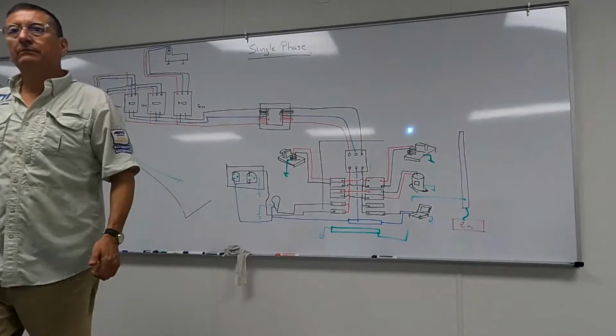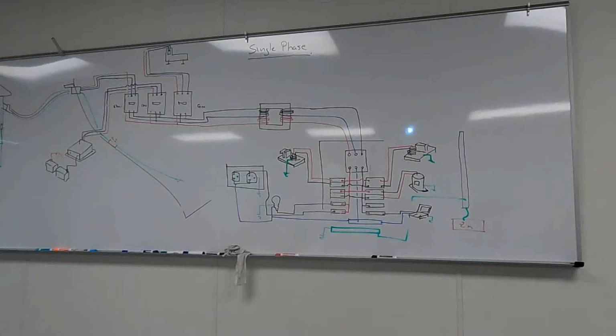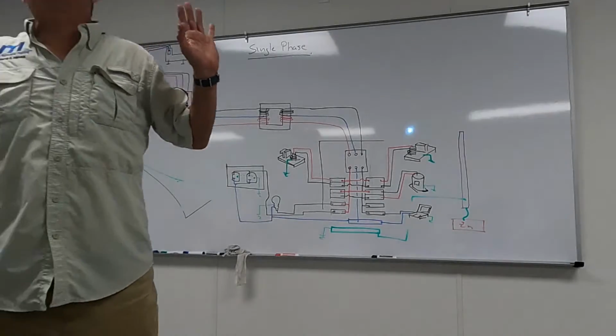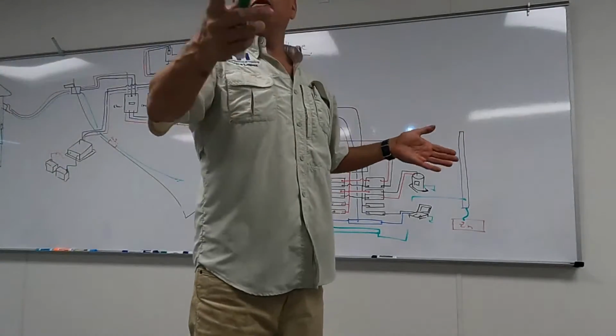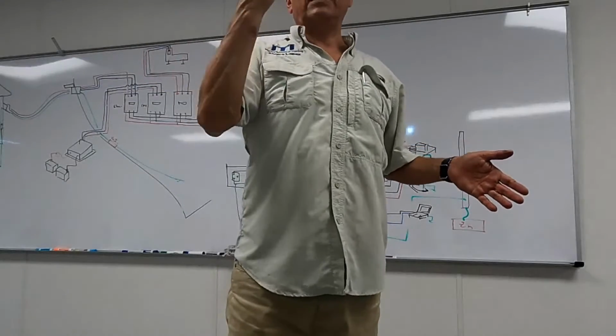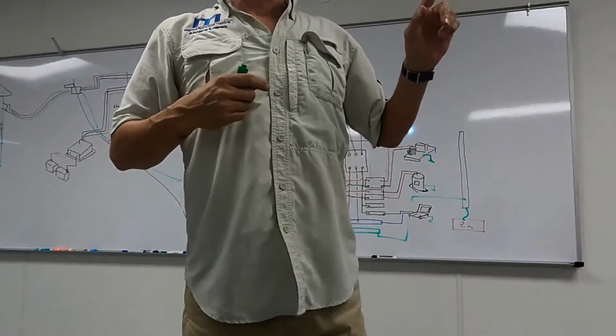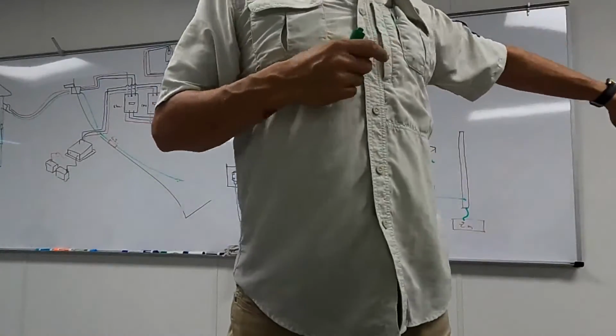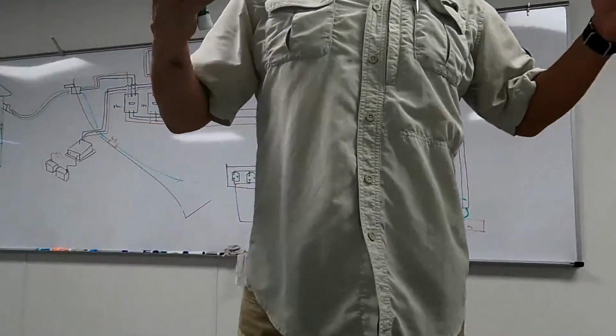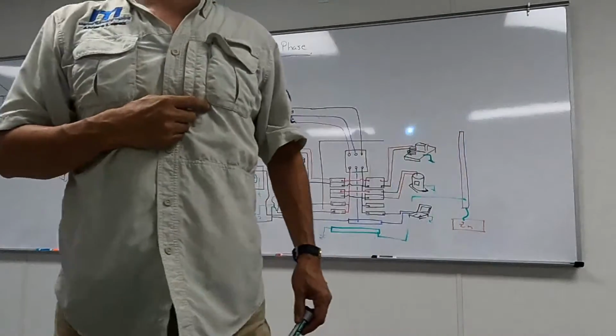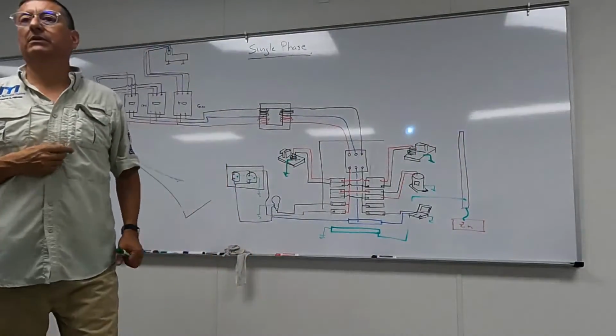Can you connect like 4 outlets to one breaker as long as you make sure? That's your decision. For example, in this room it's divided. This room has double phase because it has air condition, and half of the breakers are with one phase outlets and half with the other phase. The recommendation is no more than 5 outlets in a circuit, daisy chained. No more than 5 outlets in a circuit.